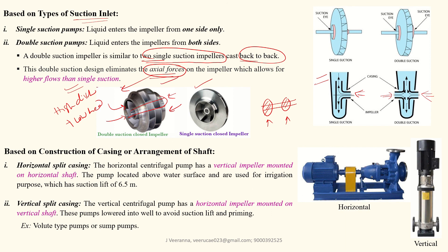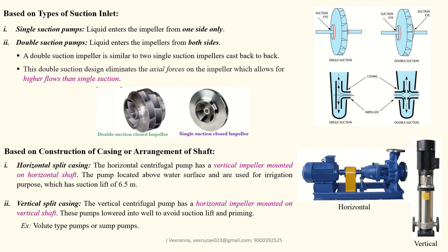The next classification is based on casing construction and shaft arrangement. In a horizontal split casing pump, the shaft is arranged horizontally (parallel to the x-axis) and the impellers are mounted vertically — these pumps are used above ground with a suction lift of up to 6.5 meters. In a vertical casing pump, the shaft is vertical (parallel to the y-axis). An example of a vertical casing pump is the volute type or sump pump.